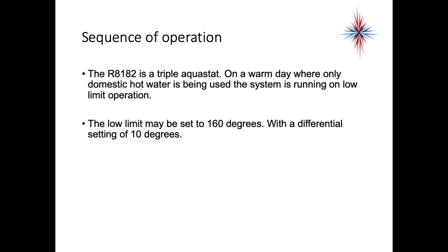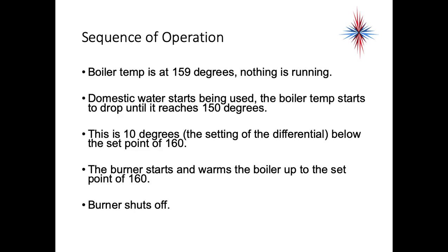The 8182 is a triple aquastat. On a warm day where only domestic hot water is being used, the system runs on low limit operation. The low limit may be set to 160 degrees with a differential of 10. If the boiler is at 159 degrees and someone starts using hot water — taking a shower, doing laundry, doing dishes — the boiler temperature drops until it reaches 150 degrees, which is 10 degrees below the setpoint of 160. The burner starts and warms the boiler up to 160, then shuts off. That 10 degrees is the differential.